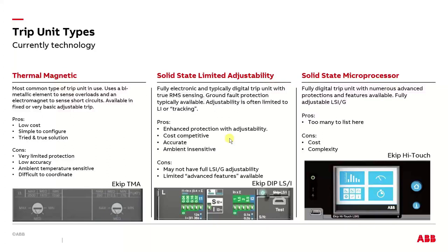Then we get to our next step up, which is a solid state breaker. And solid state's another weird term, because solid state technically meant when they transitioned from vacuum tubes to discrete electronics. So that got assigned to this type of breaker, and then that's just the way it is. So they're called solid state, and they have a pretty broad range of how that can be implemented. It could be discrete components, it could be a microprocessor. So it's wide variability. Pros would be you can get enhanced protection, and usually you get adjustable. It is a wide variance.